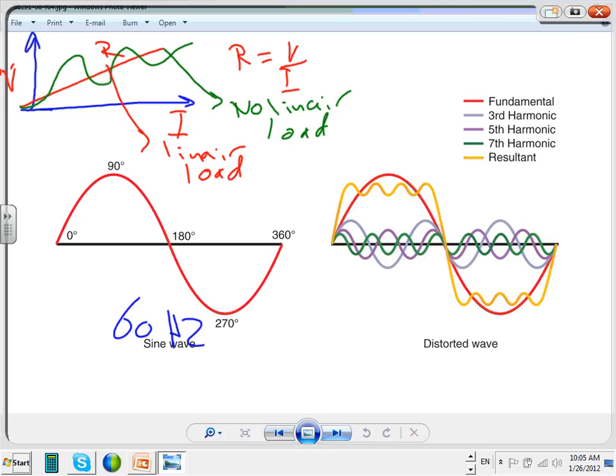Now look what happens if I plug in that printer there that has electronic equipment in it, or the ballast right above your head for this picture. When you plug them in, because they're non-linear, when you analyze the signal, look what happened. Here's the fundamental. For a 60 hertz system, the fundamental is 60. The third harmonic, 3 times 60, is 180. The fifth harmonic, 5 times 60, is 300 hertz. The seventh harmonic, 7 times 60, is 420. These are different signals at different frequencies. That's no problem so far, except they're all mixed together and fed to the same equipment.